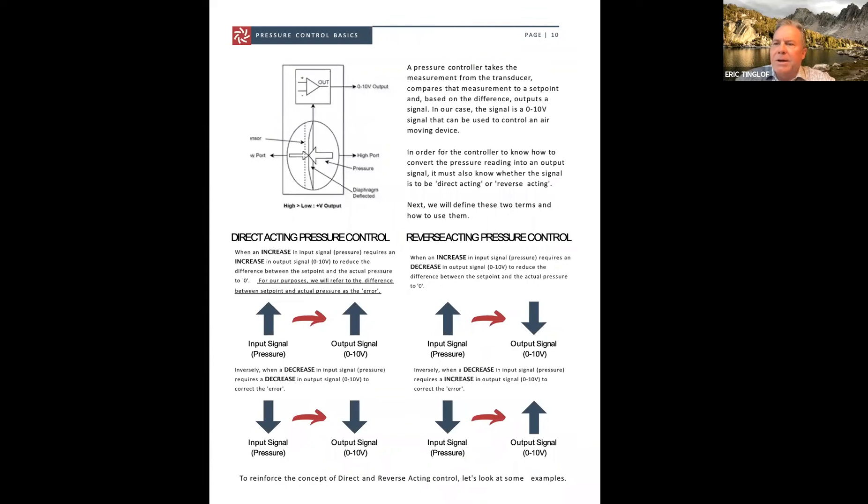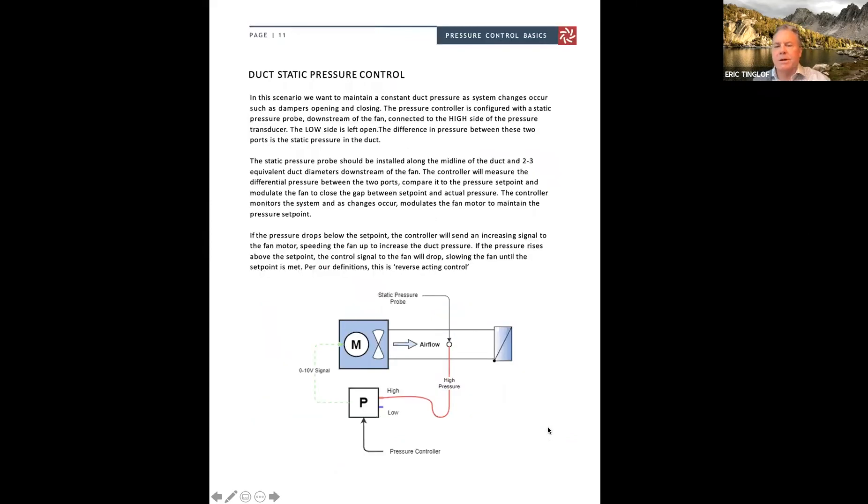And then we get into direct acting versus reverse acting. With direct acting, as the input signal, for instance pressure, is going up, the output signal that we're sending to a device or a motor also goes up in tandem with that. As the pressure goes down, our output signal also goes down. So that's direct acting pressure control. And then you have reverse acting pressure control where this is just the opposite. If pressure increases, your output signal decreases. And same way, input signal pressure going down, your output signal goes up.